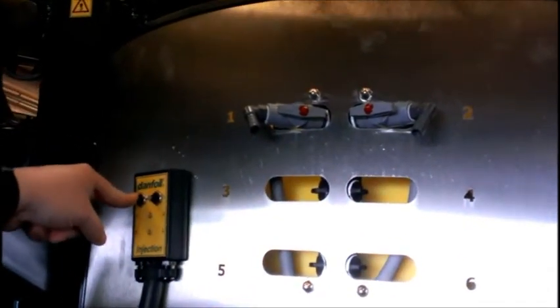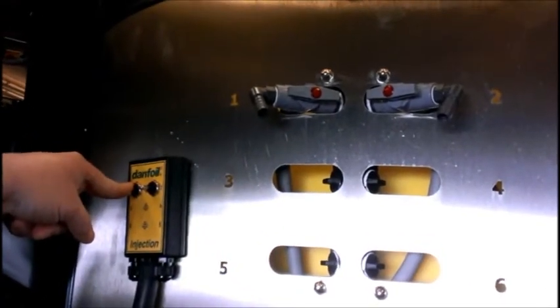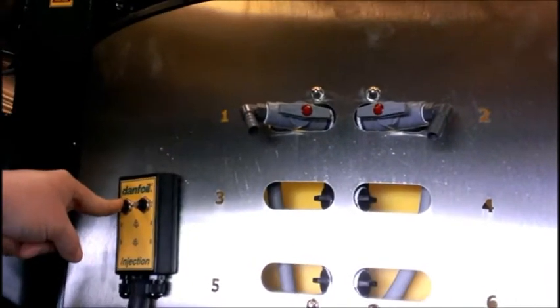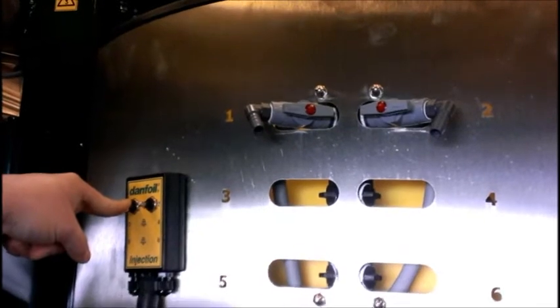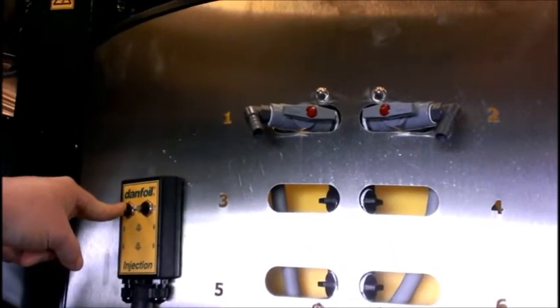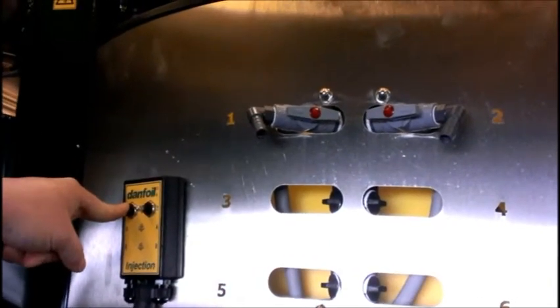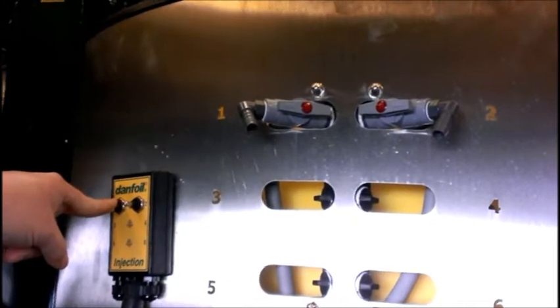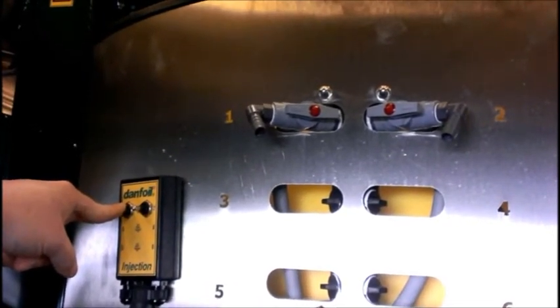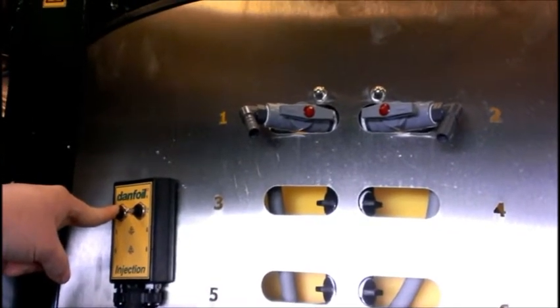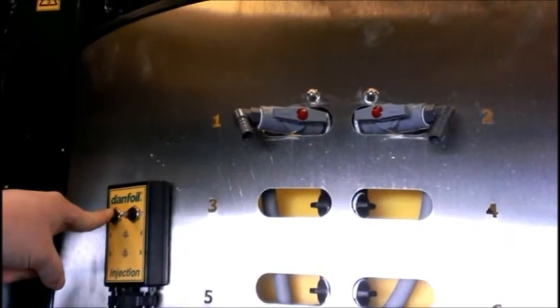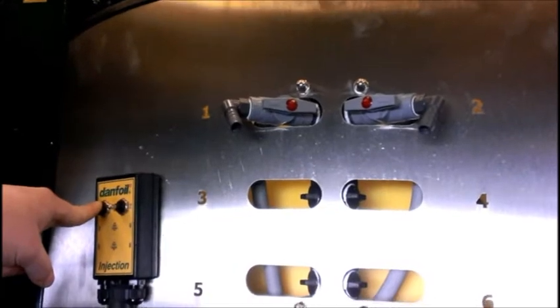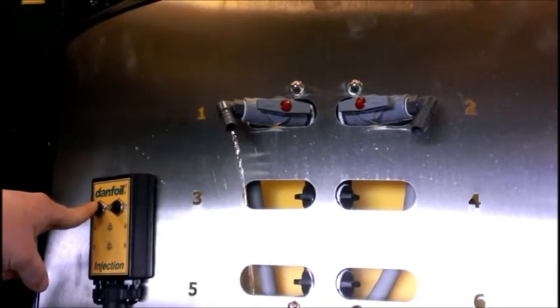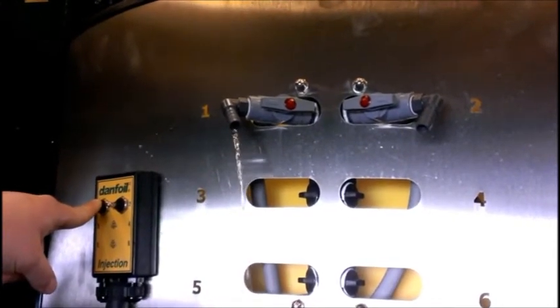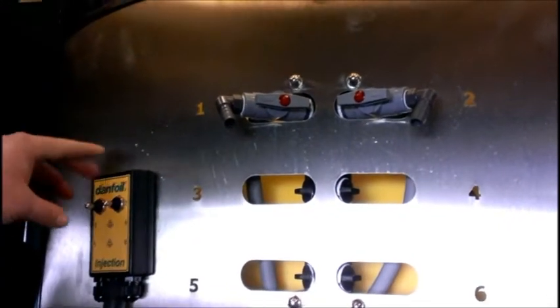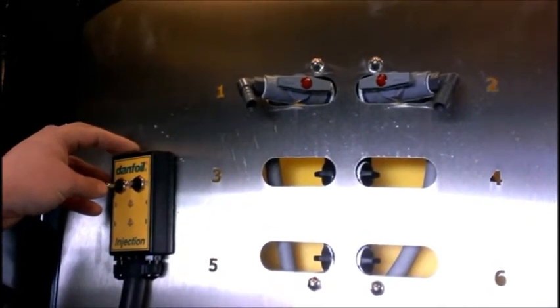Yeah. So now we are emptying the system because there is air inside the system. So we are now pulling the water directly from the tank, and now water is coming out. Water has to come out at a steady stream in order to ensure that there is no air inside the system, otherwise the calibration will be faulty. So now we have a steady stream of water coming out, which means there's no air in the system.